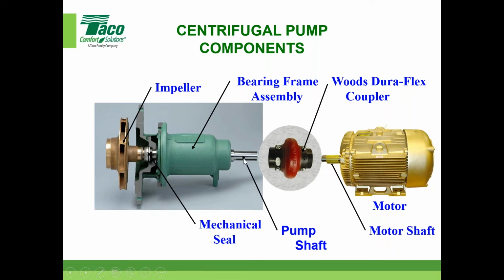I'd be remiss not to touch upon how important it is to align these shafts. The manuals that are available explain that a little bit on the base mounted units, and it's within 5 thousandths in 3 directions: horizontal, vertical, and angular. So it's very, very important to do that. I can't stress that enough. The alignment of a pump is critical for its proper operation. Again, our manufacturer's reps can make sure that's done properly, or I'm sure most contractors get involved with that on a regular basis as well.